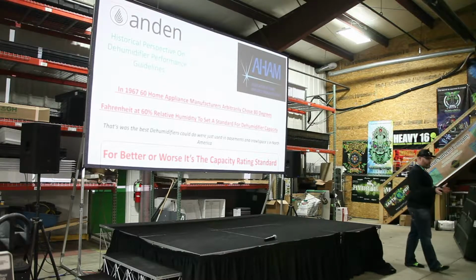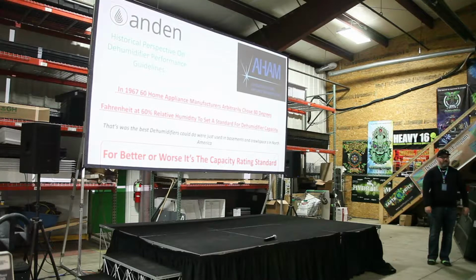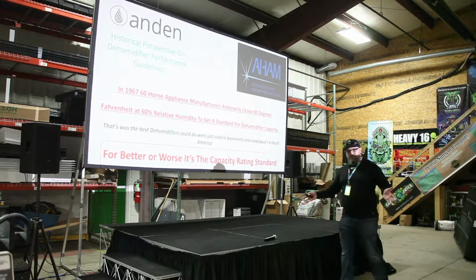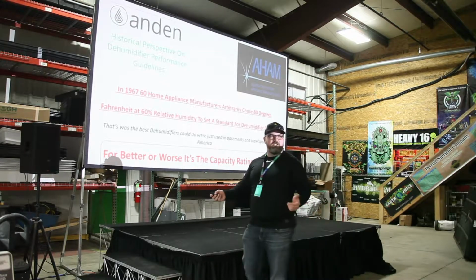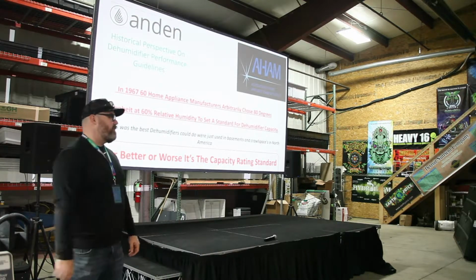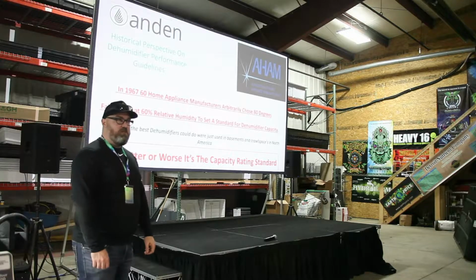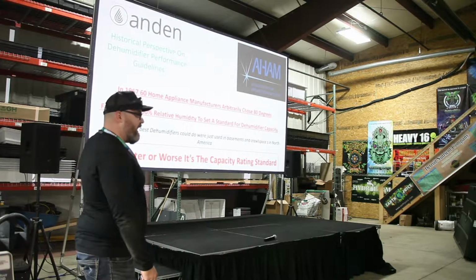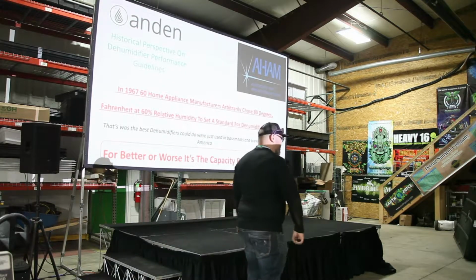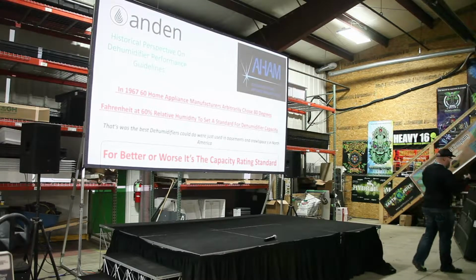You didn't have things like central air, okay? Because you didn't have central air, your house was about 80 degrees and it was about 60% relative humidity. You know, 51 years later, a lot has changed, but the rating never did. So what did every single dehumidifier company do? They built to the rating. Why wouldn't you? You build a dehumidifier that's meant to work at 80 degrees and 60% relative humidity, and you build that as best as you can, so that you get the best looking numbers, so that you can make the best looking product.